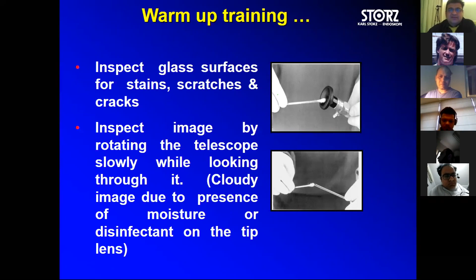Now, yes, optics can get bad because these are mechanical instruments, and over a period of time, people are sometimes telling me that, oh, I like to put the endoscope in Cidex solution, glutaraldehyde, so that it doesn't get spoiled. Please note that these endoscopes have been tested in the factory for 1000 autoclaving cycles. So one should follow an aseptic technique. You can autoclave the endoscope on the recommended autoclaving cycle of 134 degrees centigrade, 5 to 8 minutes, 3 atmosphere pressure.